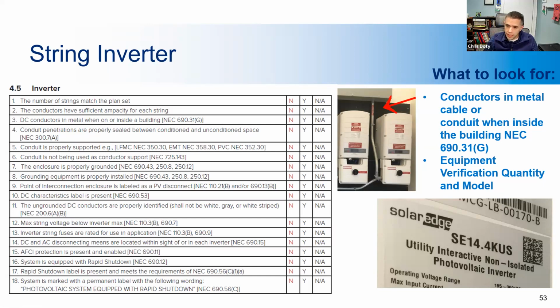In this case, the DC conductors are coming down from the roof, excuse me, and you have to verify that they're in metal conduit and that they have this red label every 10 feet. Obviously here it does, because it's not 10 feet, but you want to make sure that's the case. We'll go over the labeling section a little bit later, and that is included in that. And the metal conduit provides an additional barrier in case of an emergency, so that anyone in the vicinity will not have contact with the DC wiring, which could remain energized even if the inverter shut down.